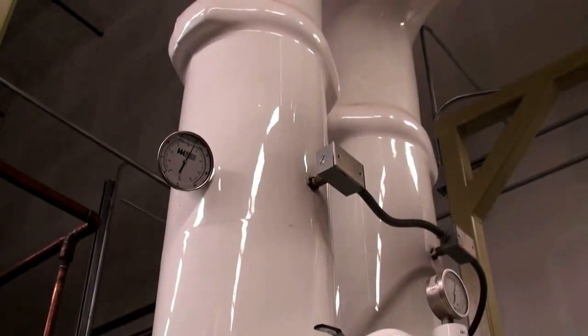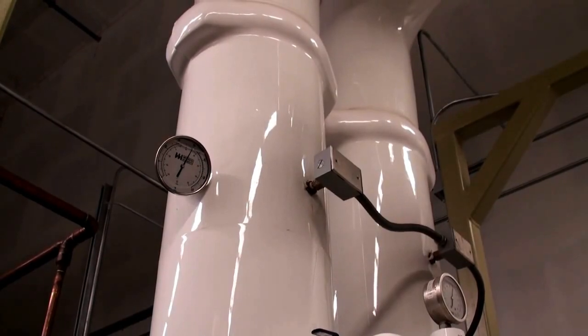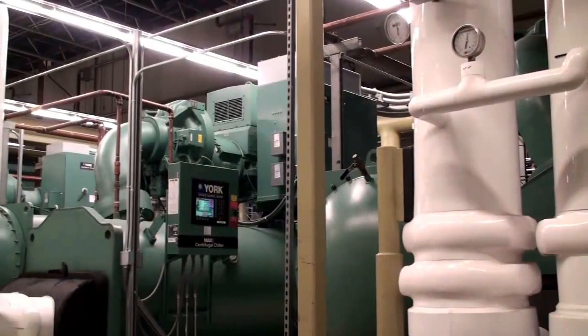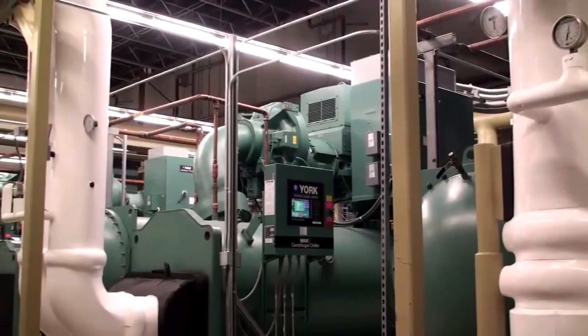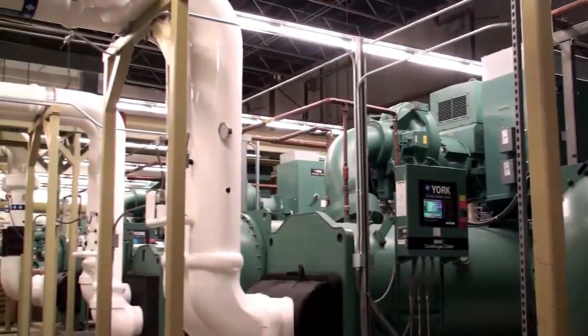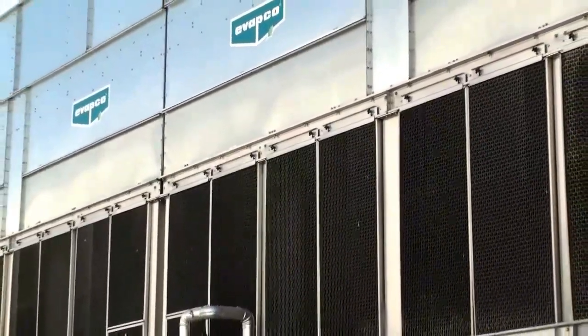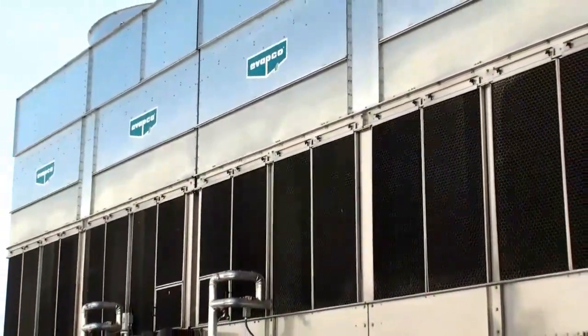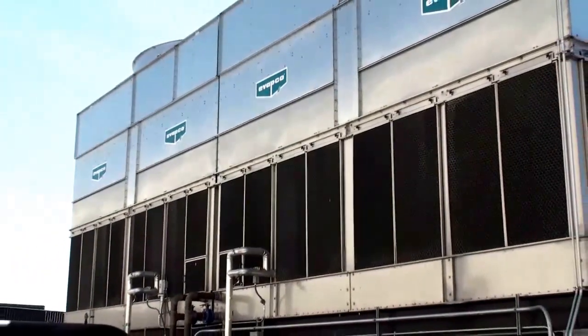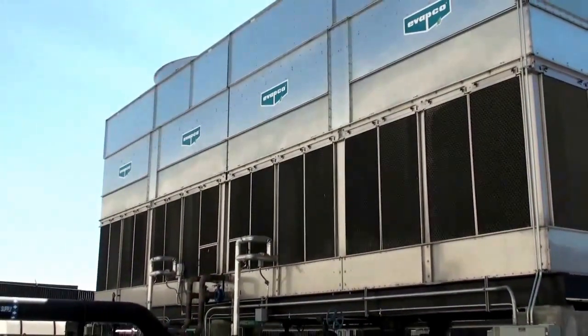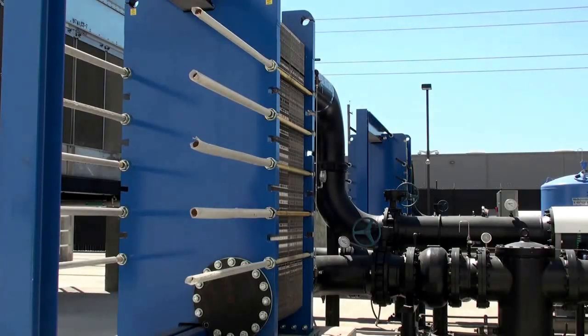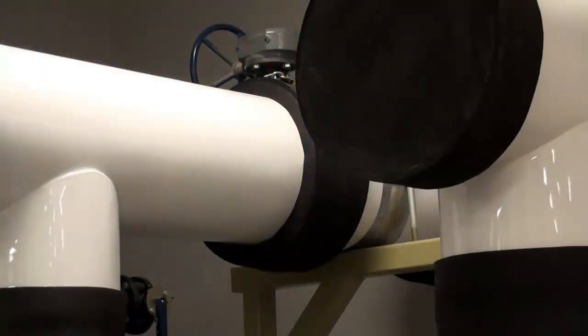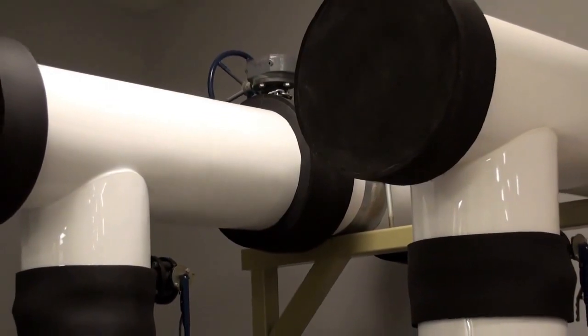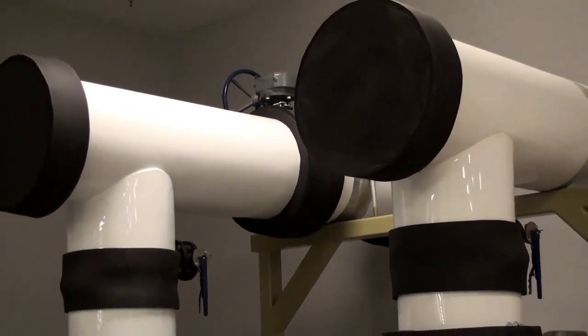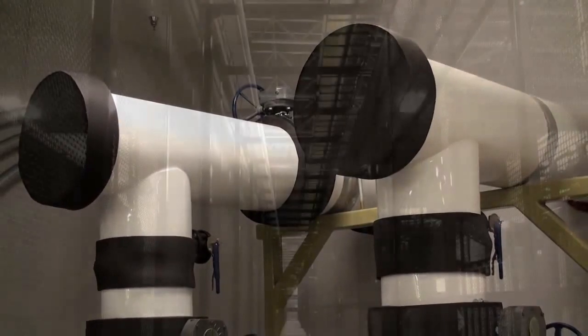Chilled water is delivered to the CRAC units and returned to the chillers via 18 and 22-inch mains. The chillers exchange heat with an open-loop system that runs outside the building to cooling towers and water-side economizers. Here, the air absorbs much of the heat from the data center, reducing the load on the chillers inside. Wells dug more than 400 feet deep by RagingWire deliver the water for cooling. This system is backed up by the city's utility water supply. Here, 22-inch mains carry chilled water between buildings. This makes it possible for Building 2 to run from Building 1's cooling plant.